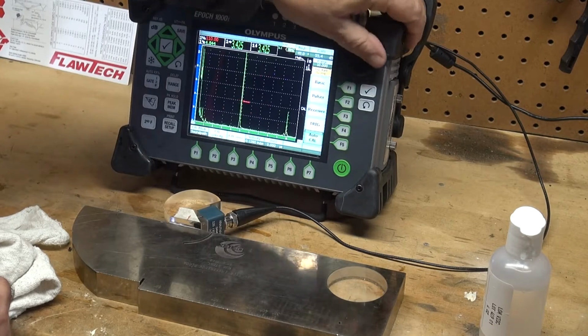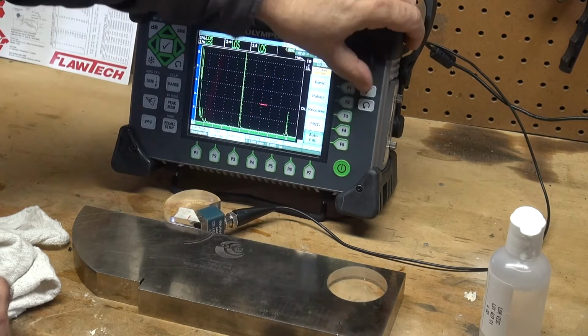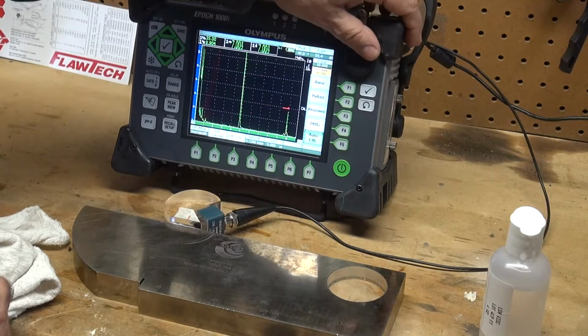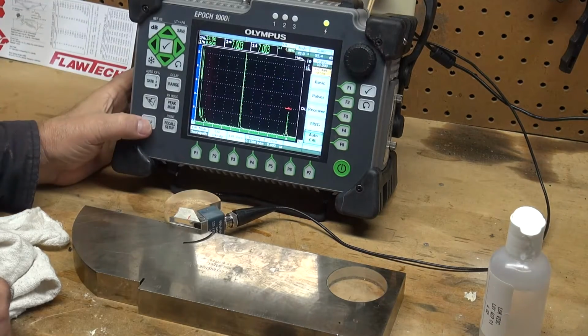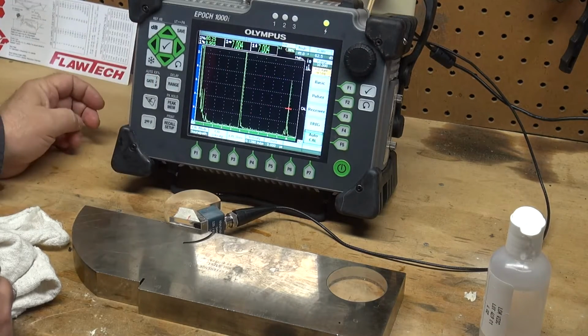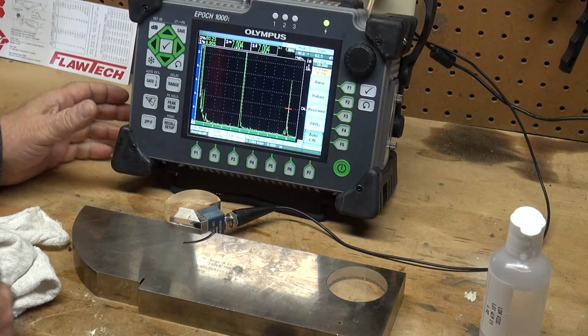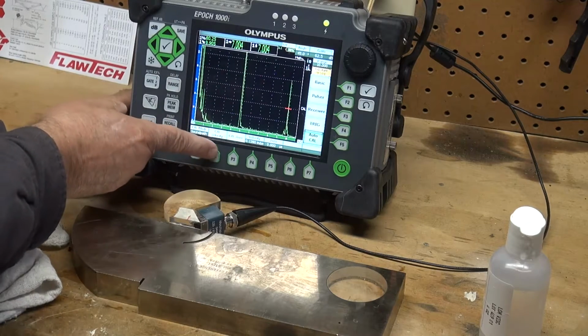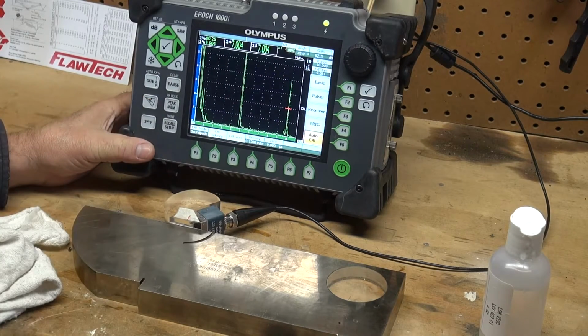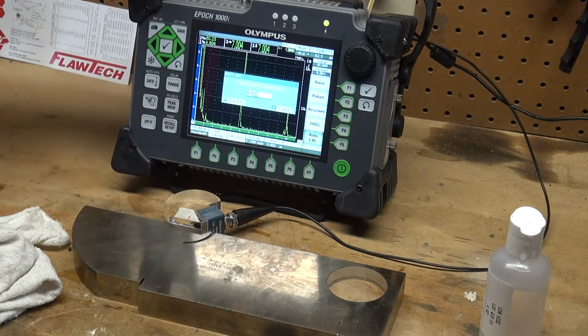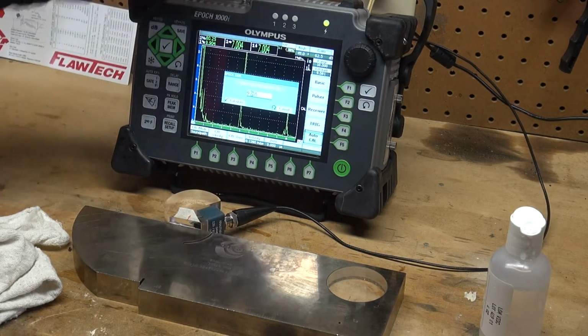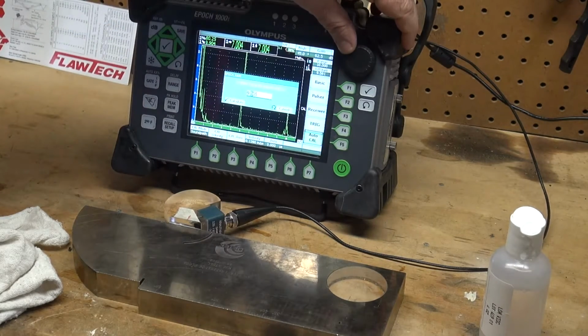Move the gate over to hover over that 9-inch radius. Second function, auto 80. Take it to 80% full screen height. Now I'll press F2, which is my cal velocity. And I have to tell the machine that it is looking at a 9-inch sound path.